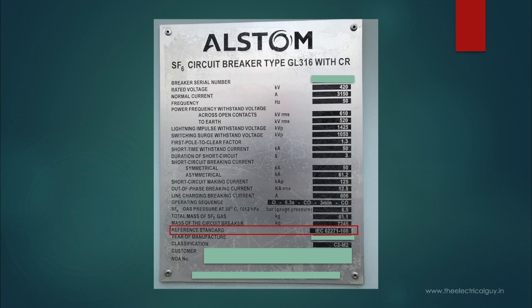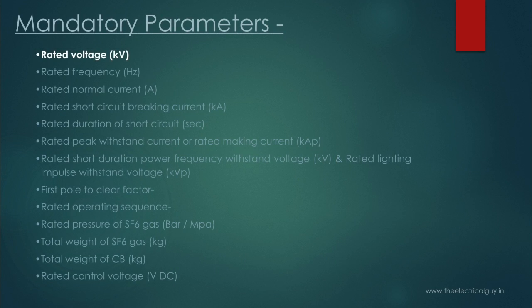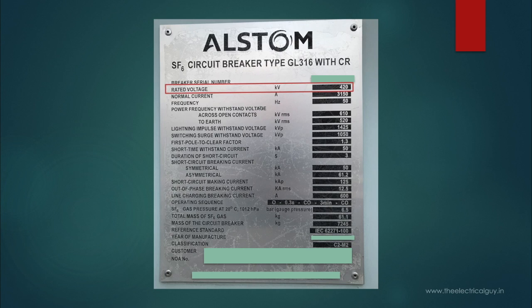The relevant standard as per which the breaker is manufactured. Then rated voltage — the highest system voltage for which the breaker is designed, given in kilovolt RMS referring to phase-to-phase voltage of a 3-phase system. Most people get confused between rated voltage and normal voltage. Rated voltage is the highest voltage for which the equipment is designed, whereas normal voltage is the voltage which normally remains on the system. So 420 kV is the rated voltage and 400 kV is its normal voltage.